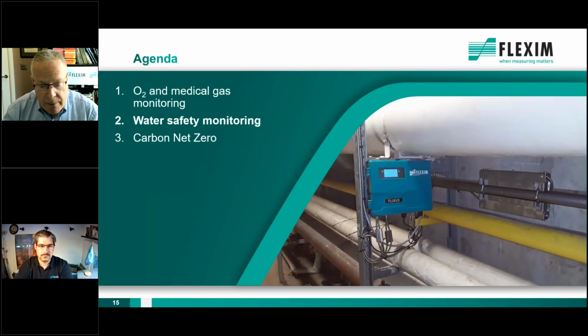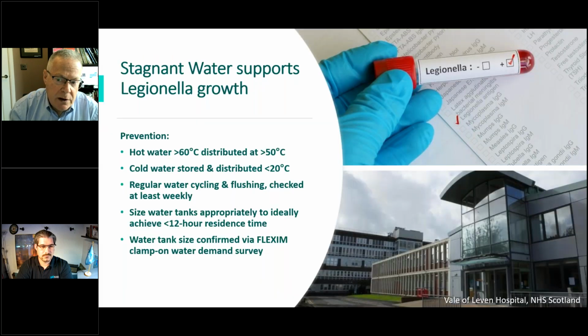That led us on to other applications. One of the key critical issues with any building, whether it's hospitals, universities, libraries, etc., is that if you've got an air conditioning system or any water system, any standing water supports Legionella growth. And obviously, I'm sure every facilities manager knows that this is a key and critical point of control. So you've got to keep your hot water above 60 degrees C and distribute it at more than 50. Cold water should be stored and distributed at lower than 20 degrees C.